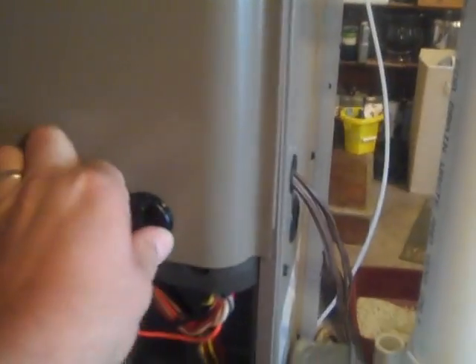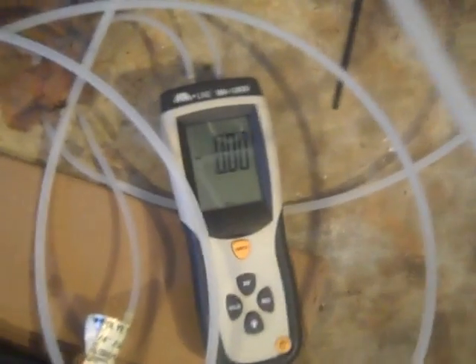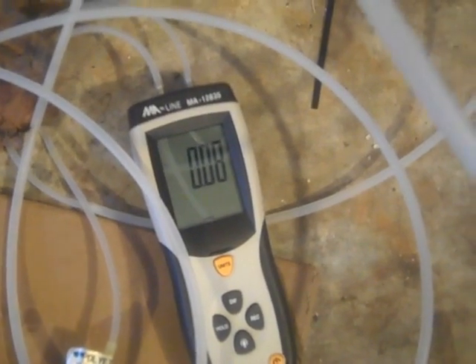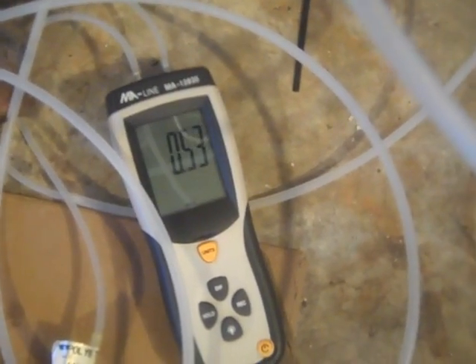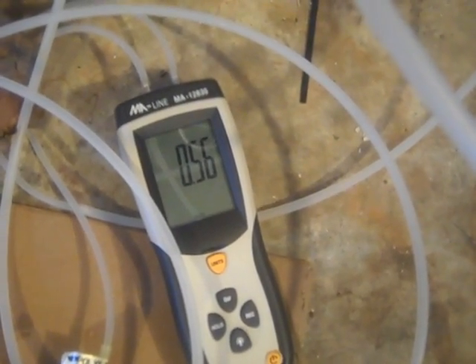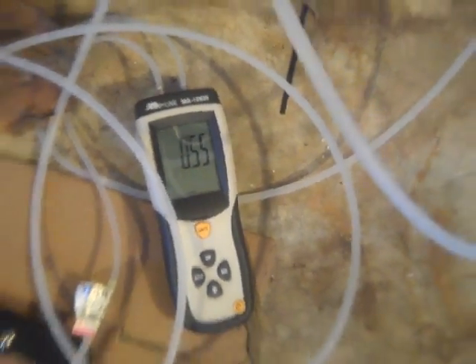We'll look on here and find out which is medium. Medium is gray, so we're going to go ahead and stick that back on low cool. This is not, this is a single stage cool unit, so that won't be used, but here's gray. We're going to put our door back on. We're showing zero, zero. We're going to turn it on and check medium. Medium .55. We'll record that.